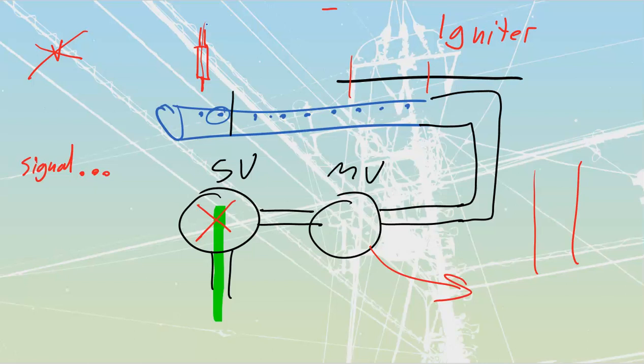You're going to have to try an ignition cycle. You're going to watch where that spark is, and you're going to say, yeah, the spark looks good, I'm seeing good spark, and it's over top of that. If not, it's got to be something different. If it is a hot surface igniter, all you need to do is verify that that thing heats up to the point of being white hot, and that once again, wherever it's sitting over top of, those gas orifices are clean, so that we can actually jet some gas onto the white hot surface to start that thing up.